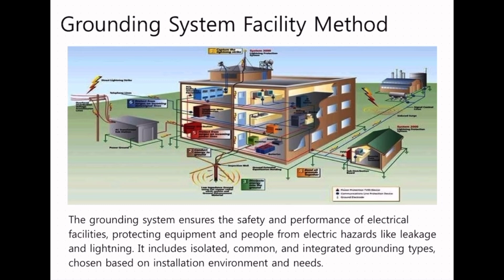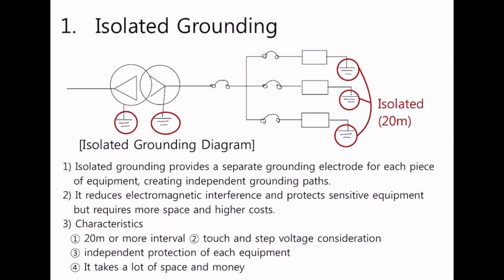Isolated grounding. Definition. Isolated grounding involves installing a separate grounding electrode for each piece of equipment that requires grounding. This method reduces electromagnetic interference, EMI, and is advantageous for protecting sensitive equipment. System diagram. The system diagram shows separate grounding electrodes connected to each piece of equipment, such as transformers, communication devices, and control systems, emphasizing an independently isolated structure.